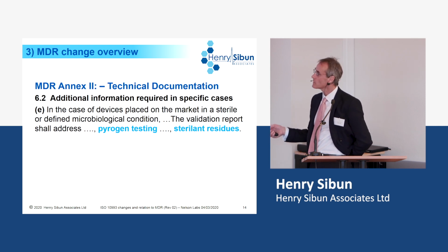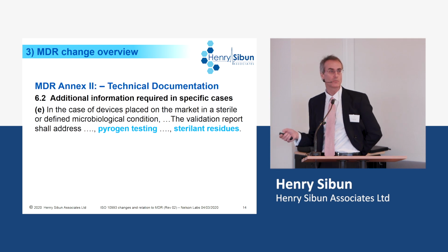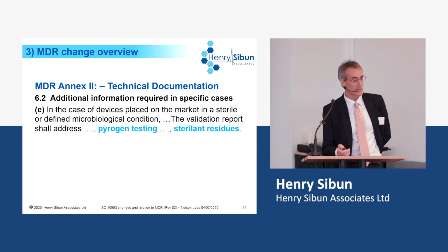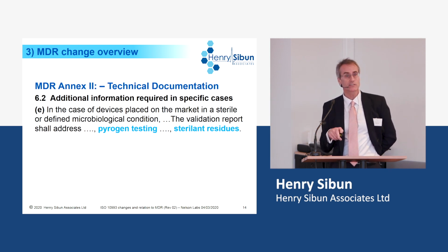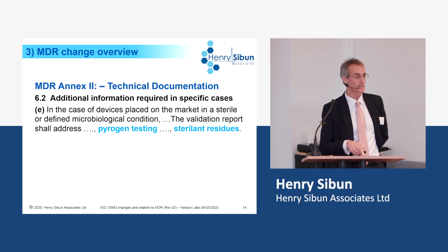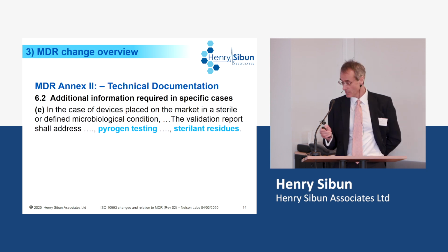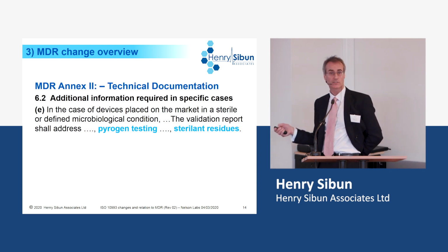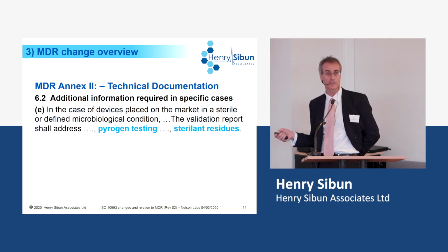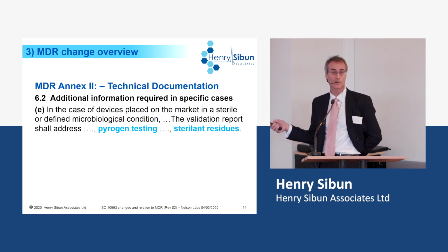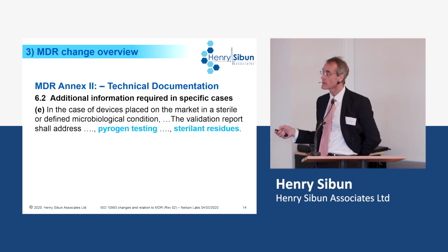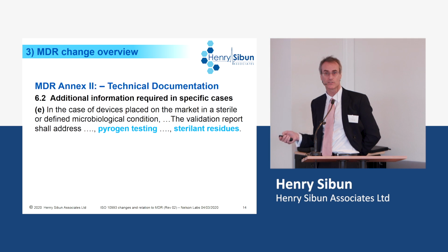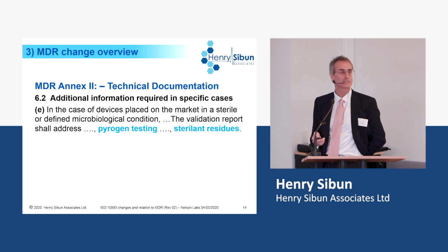But the question people are asking is, does it mean it's mandatory to do pyrogen testing? Well, from a notified body perspective, no. Okay, this clause deals with sterile devices. You need to consider material-mediated pyrogenicity based on the materials you're using. And for sterilization, you would consider endotoxins from a sterility point of view. Okay, they're two different things. So although it does state here you will have to do pyrogen testing, from a notified body perspective, at least from talking to notified bodies, they're looking at this as more aimed at LAL testing for endotoxin. Okay, you might need material-mediated pyrogen testing, but that's a separate endpoint.